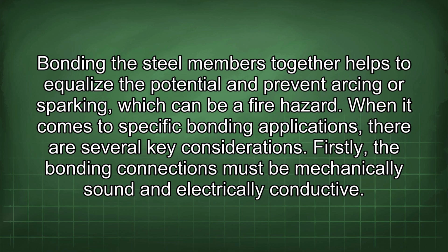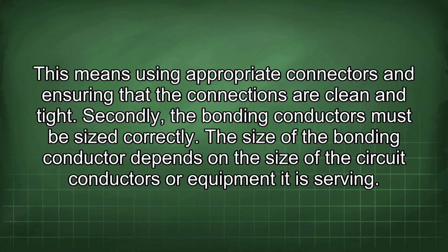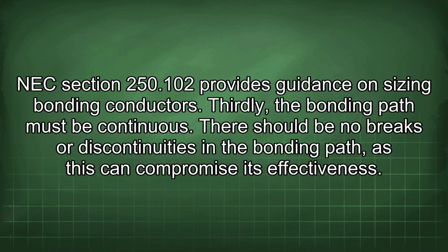When it comes to specific bonding applications, there are several key considerations. Firstly, the bonding connections must be mechanically sound and electrically conductive. This means using appropriate connectors and ensuring that the connections are clean and tight. Secondly, the bonding conductors must be sized correctly. The size of the bonding conductor depends on the size of the circuit conductors or equipment it is serving. NEC Section 250.102 provides guidance on sizing bonding conductors. Thirdly, the bonding path must be continuous. There should be no breaks or discontinuities in the bonding path, as this can compromise its effectiveness.